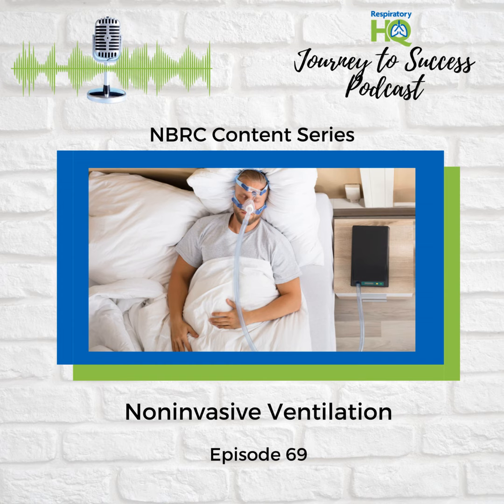And the opposite, too much flow. Yes, if the pressure seems inadvertently high or the patient complains it's hard to exhale, the flow might be set too high and you'd need to decrease it. And a couple of other little things. If a water-based humidifier is used, the pressure can drift down as the water evaporates. Need to keep an eye on the water level. Exactly. And some older systems used a ball-bearing resistor. Those had to be kept perfectly vertical, or you'd lose all the pressure. Good to know. Okay, so CPAP has its quirks.